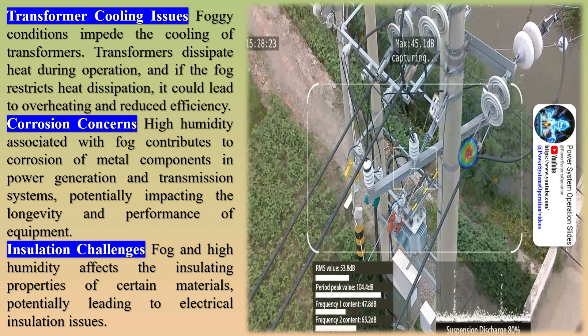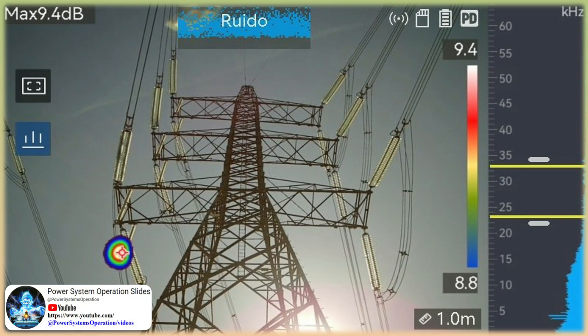Corona effect results in energy loss as it dissipates energy in the form of corona discharge, reducing the overall efficiency of power transmission. This corona discharge also produces audible noise, which is disruptive especially in residential areas. Corona discharge also results in deterioration of insulators and transmission lines over time, reducing their lifespan and increasing the frequency of maintenance. Additionally, foggy conditions impede the cooling of transformers, potentially causing overheating and reduced efficiency, while high humidity associated with fog contributes to corrosion of metal components in power generation and transmission systems.